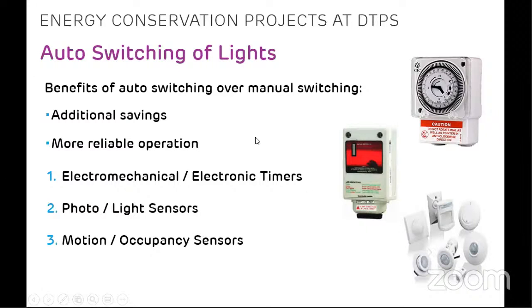So there are three different types of switching systems. First was the old one which we used earlier, which is electronic or electromechanical timers. They switched on at fixed timings. If you set it at 6 a.m., the lights will switch off, and at 6 p.m. the lights will switch on. Likewise, you can program it. Now we have installed a new technology, which is photo sensors or light sensors. These sense the light in the ambient or natural conditions, and according to that the lights are turned on or off.